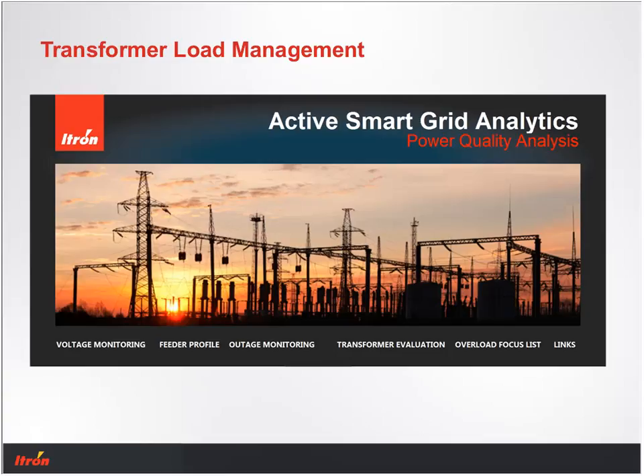So if you provide that connectivity, just essentially that these 6 service points are on this one transformer, that one transformer maybe is a 25 kVA overhead transformer that we have some curves, or you can even put your own parameters in. We can then calculate the loading on those in quite a bit of detail. Again, just checking with your maximum kVA usage over the rated nameplate, which is a valid but sort of simplistic way of looking at it.